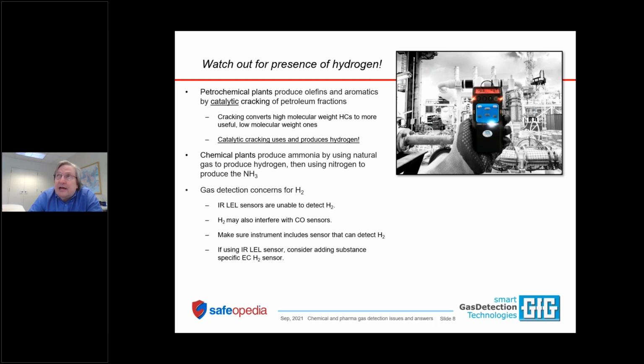If you have a hydrogen nulled or low hydrogen sensitivity CO/H2S sensor or single channel CO sensor, it depends on the design, but in a dual channel low hydrogen interference CO/H2S sensor, probably you're going to see a relative response of 20%. With a single channel CO sensor that has been deliberately manufactured to really reduce the cross sensitivity, it might only be 5%. It's not going to be zero. So when a manufacturer uses the term hydrogen nulled CO sensor, it's not nulled all the way down to zero. About as good as it's going to get is a 5% relative response.